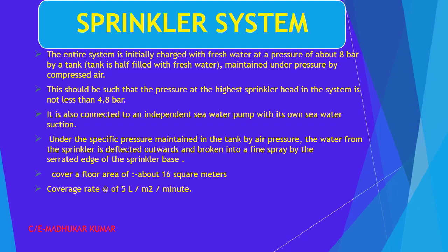It is also connected to an independent seawater pump which has its own seawater suction. Suppose the fire is large and the fresh water is being exhausted or finished, then you have the seawater which is there already. So the seawater pump also starts and starts giving water to the system. Under specific pressure maintained by the tank and by the air pressure, the water from the sprinkler is deflected outwards and broken into a fine spray by the serrated edge of the sprinkler base. Basically, the spraying of the water is done with the help of the nozzles, or you can say the sprinkler heads, which are designed for that, and the deflector plates are doing the work.